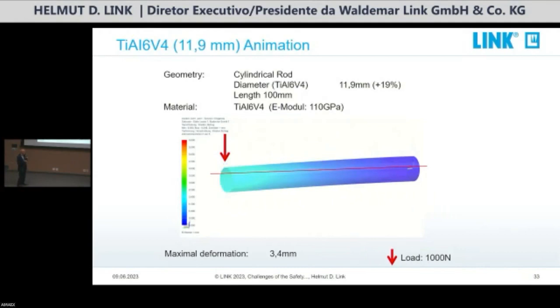This means that an increase in diameter of about 19% is already sufficient to achieve the same flexural stiffness in a titanium stem as in a slightly thinner cobalt chromium stem. Stem thickness is important. This is also very important to tell the surgeon.